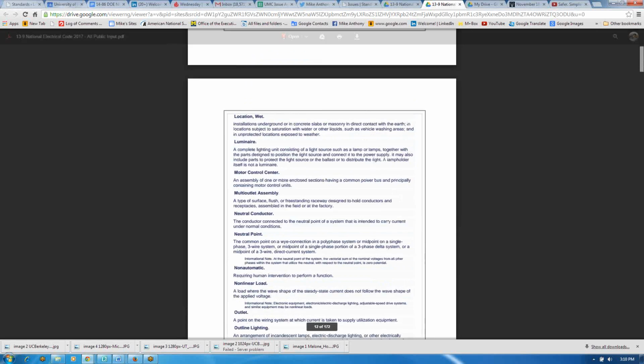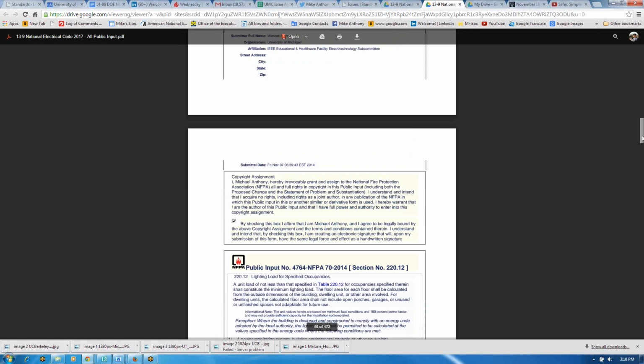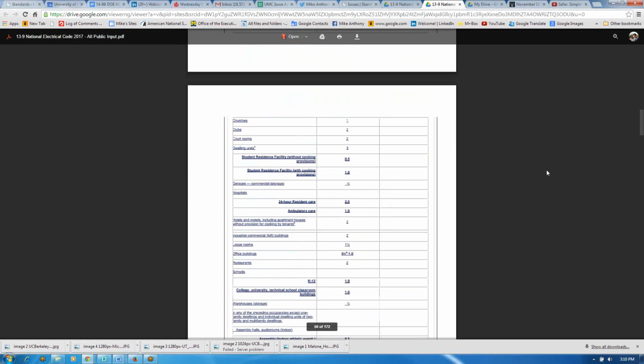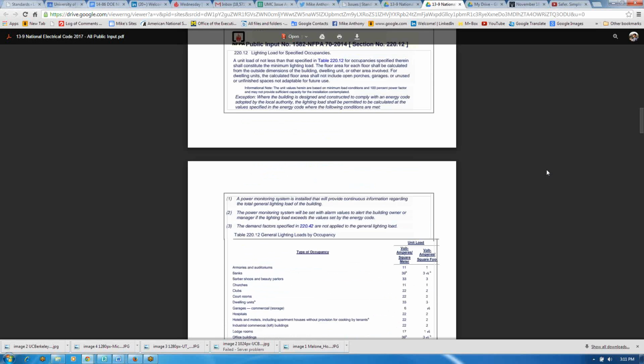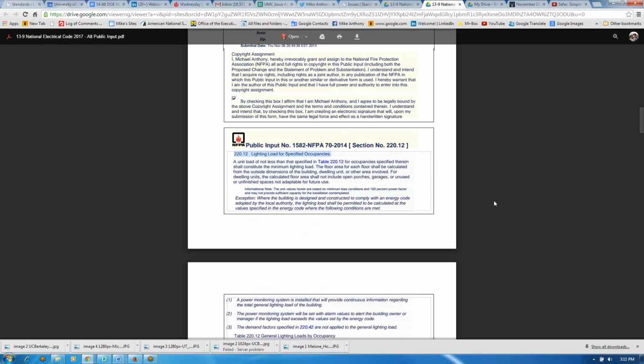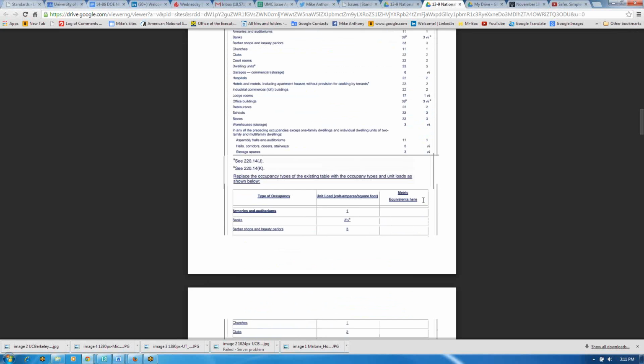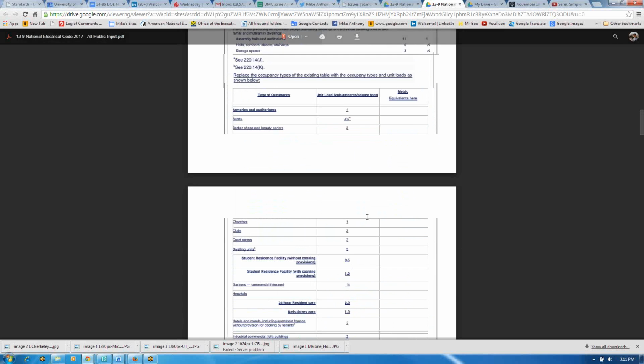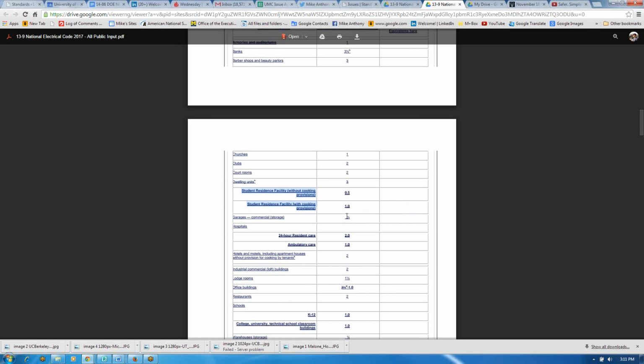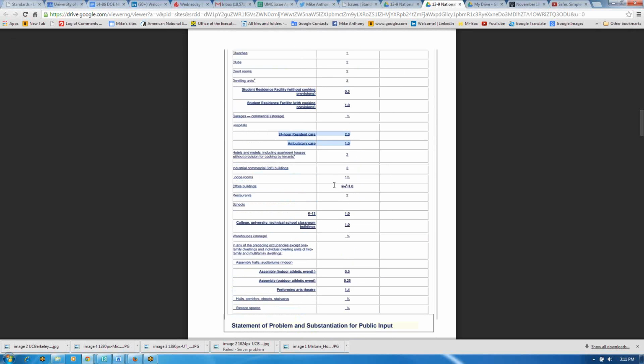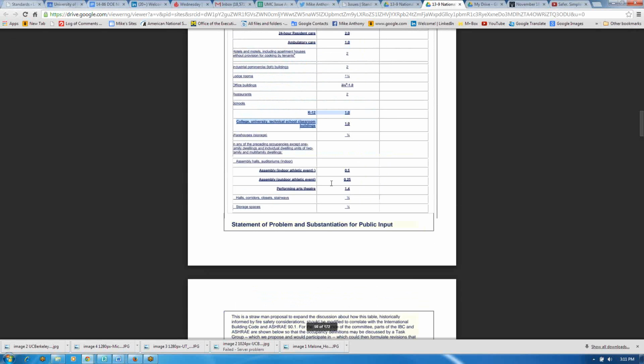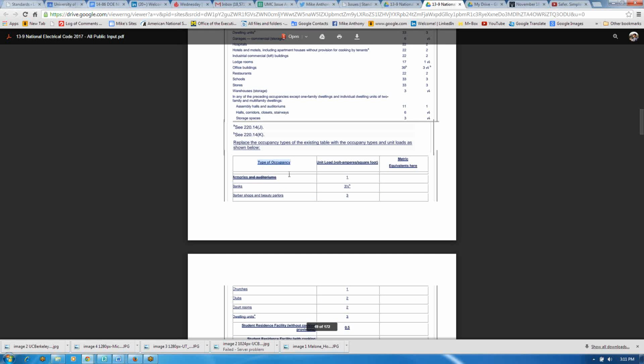To give you an idea of what we did on 220.12, Article 220.12—we tried to drive in the ASHRAE standard, though it may not be easy to see here. This is the table designers use for designing lighting supply circuits. We discovered that a lot of these occupancies aren't relevant or used very often, but in our industry these are occupancies that are actually in the International Building Code.